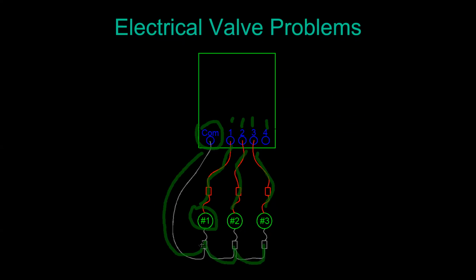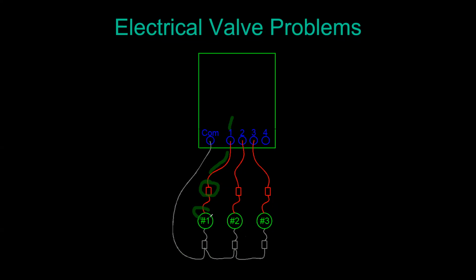That wire is connected to one wire of all the solenoids on the valves. And honestly, they're not usually individually done like that. They will usually pull the wire from this one here and the wire from that one here and just use that one connector. So let me erase these real quick because I want to do another drawing here. Okay. So now if the problem is only affecting station 1 and you know it's electrical, because when you manually actuate the valve at the valve itself, it does turn on. So now what we're going to do, if it's only affecting number 1, it's a broken wire here, it's a bad wire connection here, or it's a bad solenoid on this valve.